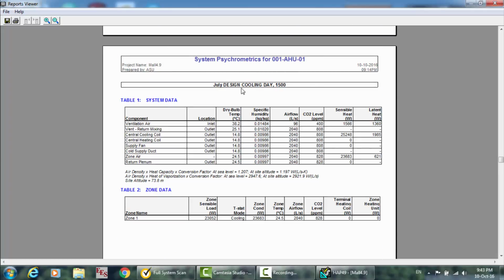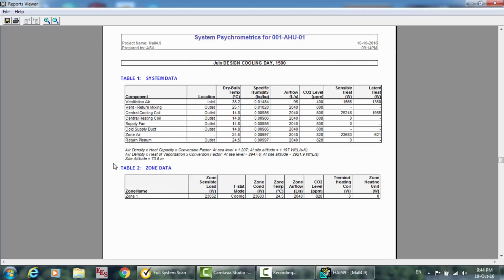And here the July design cooling day. This is the peak at 15, at 3 p.m. This ventilation air, the inlet, and the temperature of the inlet. And here is the outlet and return mixing, and the central cooling coil. It will be 14.8. The specific humidity, airflow, CO2 level, sensible heat and latent heat, supply fan and cold supply duct, zone air. You have to recheck everything. If you have losses, if you have something wrong, please recheck it and go and recalculate it.